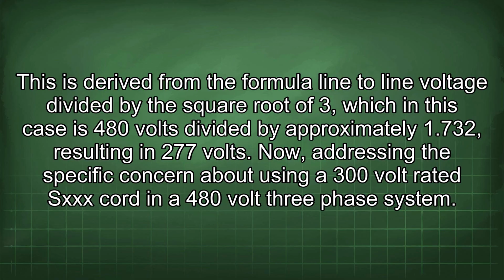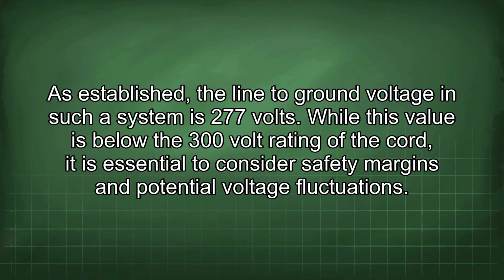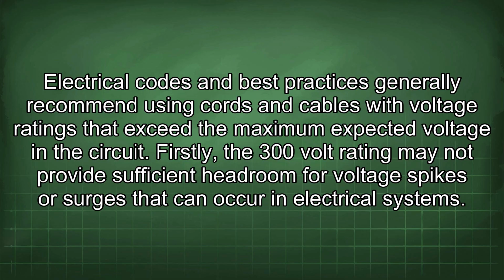Now, addressing the specific concern about using a 300-volt rated Sxxx cord in a 480-volt three-phase system. As established, the line-to-ground voltage in such a system is 277 volts. While this value is below the 300-volt rating of the cord, it is essential to consider safety margins and potential voltage fluctuations. Electrical codes and best practices generally recommend using cords and cables with voltage ratings that exceed the maximum expected voltage in the circuit.